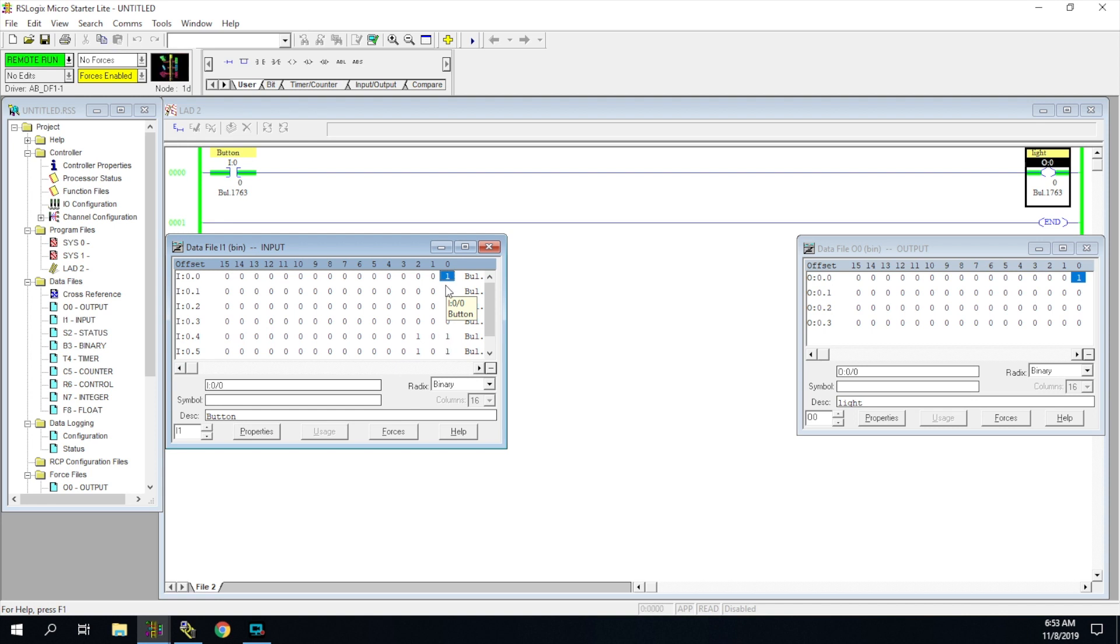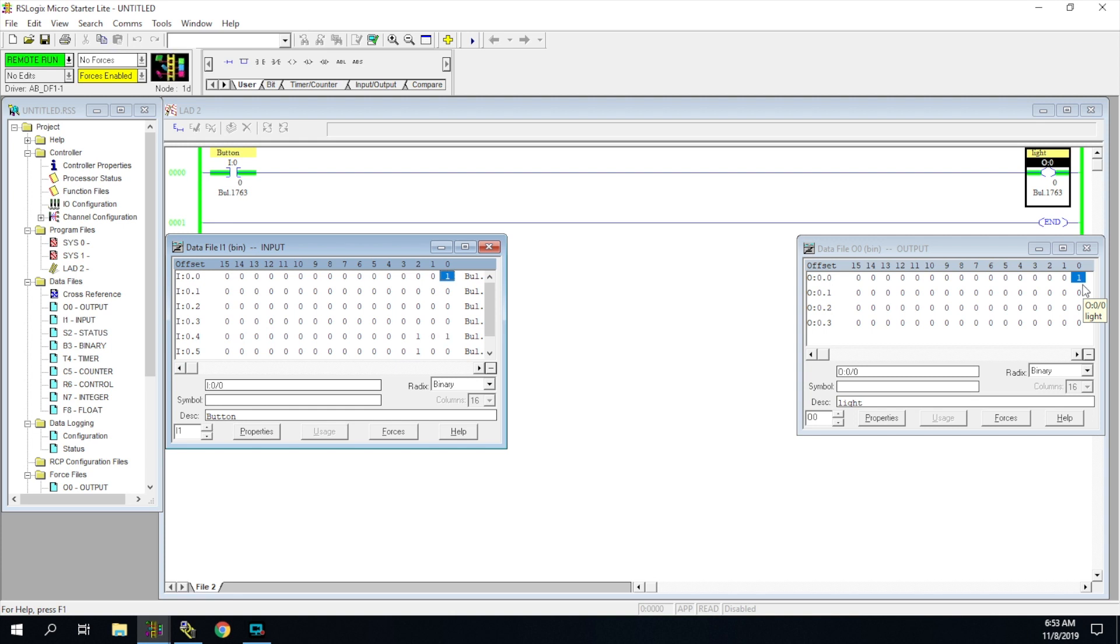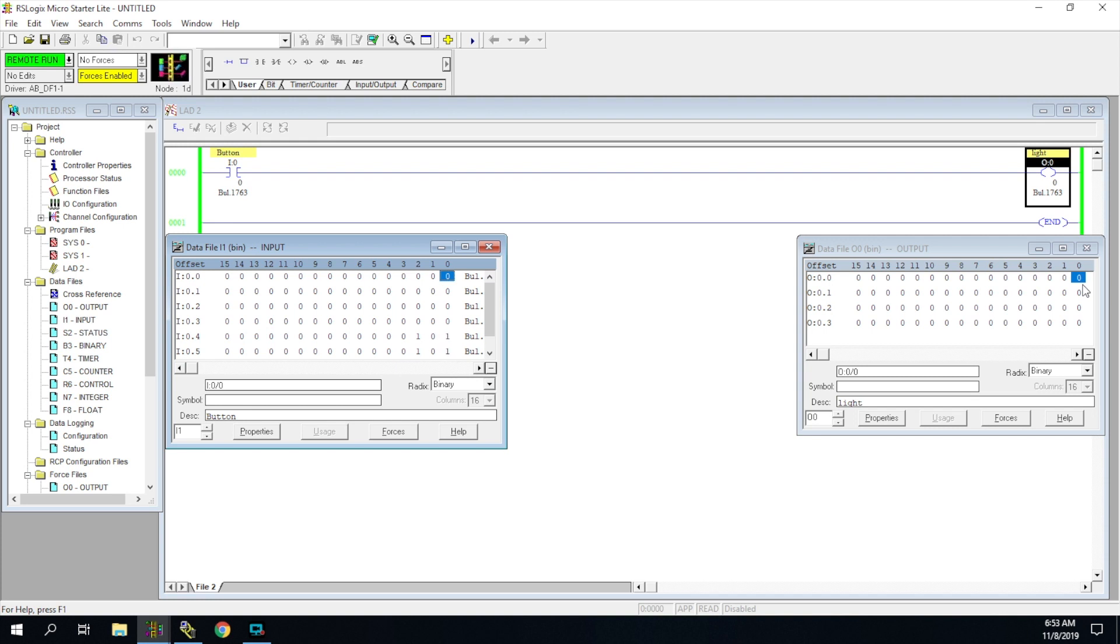We're going to be doing some test questions on that, and that's something I really want you to get: we press the button, the terminal gets 24 volts. It's going to change that internal bit from a zero to a one, and then the instruction is going to be based off of that one or a zero. Now I want you to also notice I've got a one here now. So this light is now true, so I've also got a one here. If I turn it off that becomes a zero, if I turn it back on it becomes a one. We're going to be talking a lot about bits, and these are just an internal bit. Literally it's just a bank of numbers that are connected to those input terminals or those output terminals, and it's just kind of letting us know what's happening.